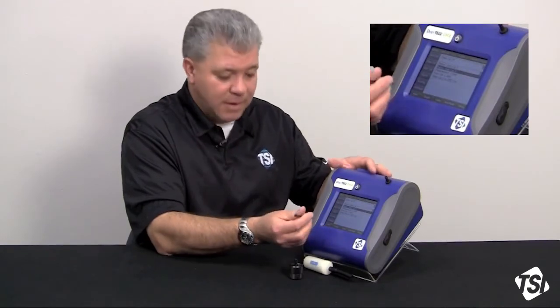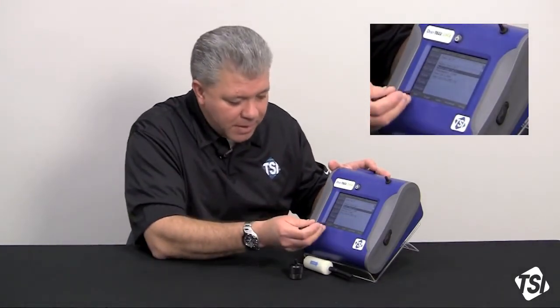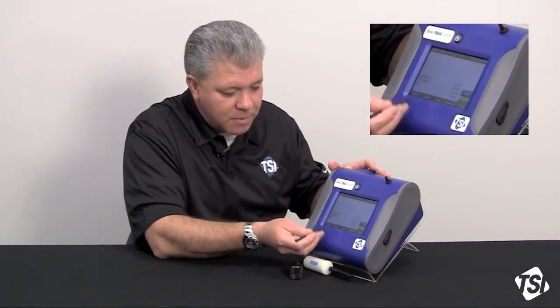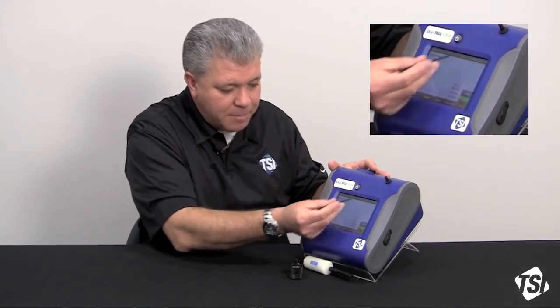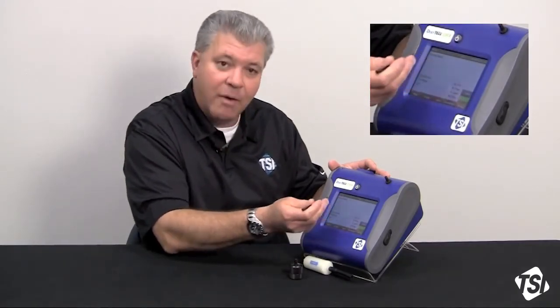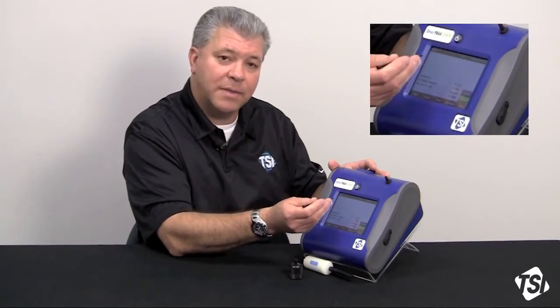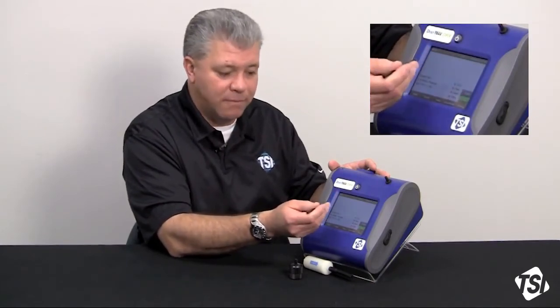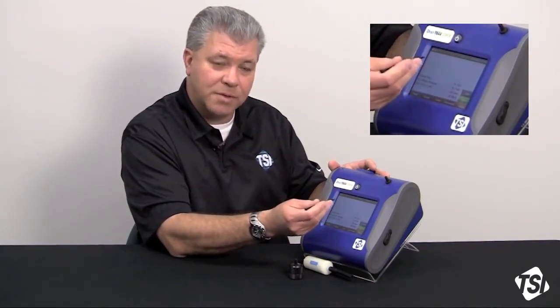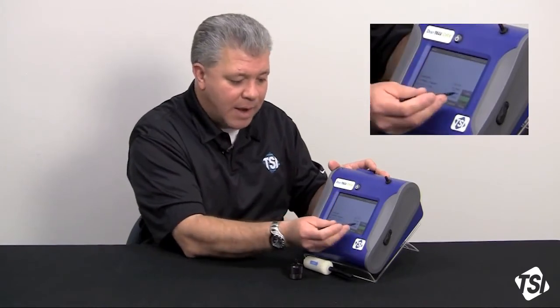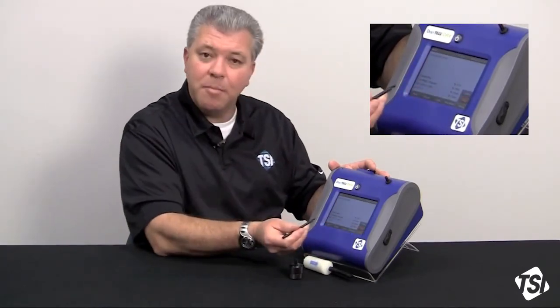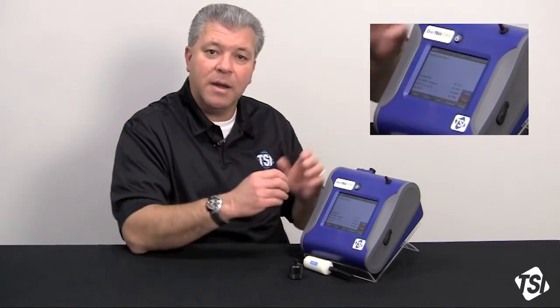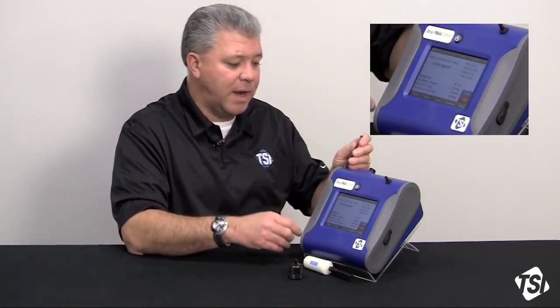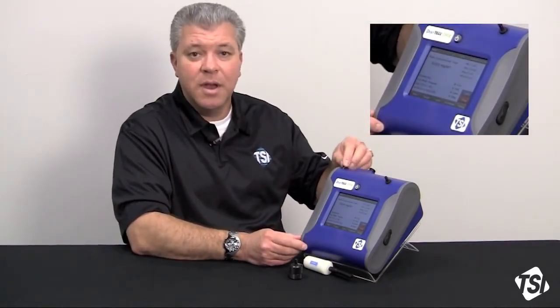So now all we simply have to do is go back to the main screen. It's going to update the memory, so now it's inputting that the size correction factor is 1.4. The photometric correction factor is still 1.0. And now, when you press the start button, the instrument turns on, and the instrument's response has changed to the size distribution of the aerosol in the environment that you're monitoring.